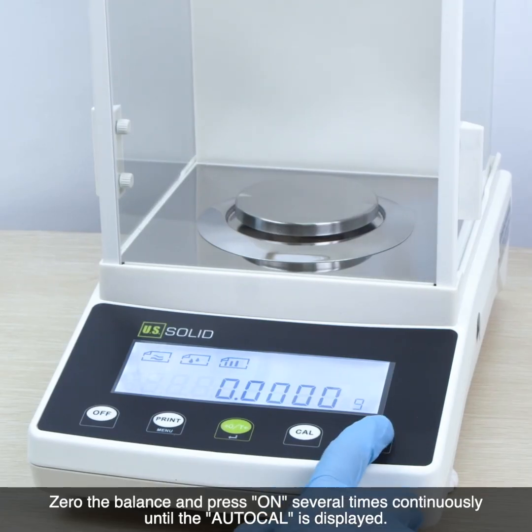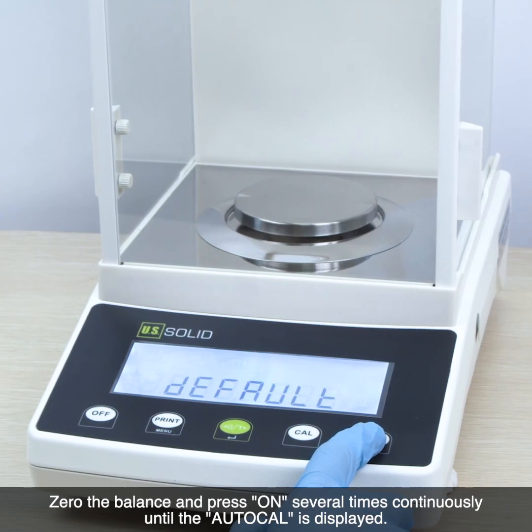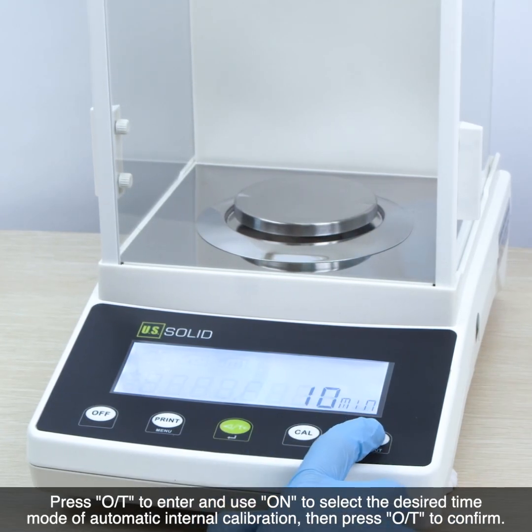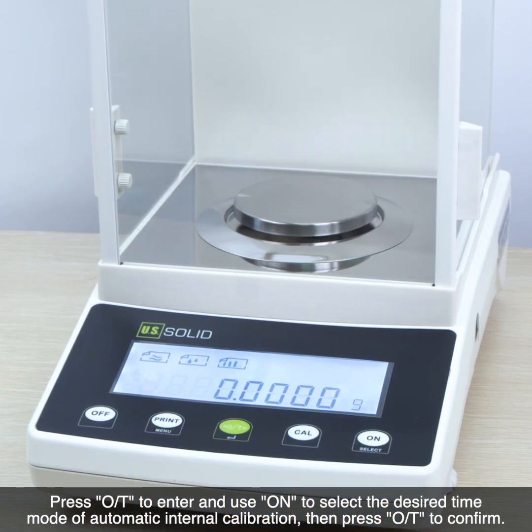Zero the balance and press on several times continuously until the AUTOCAL is displayed. Press OT to enter and use on to select the desired time mode of automatic internal calibration. Then press OT to confirm.